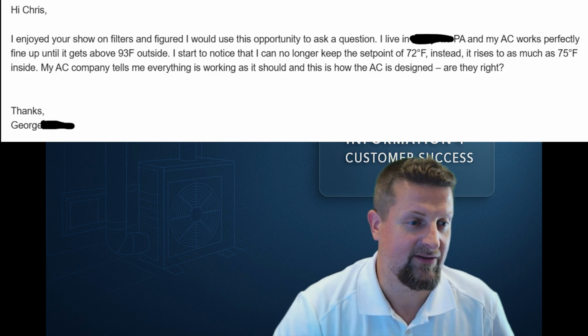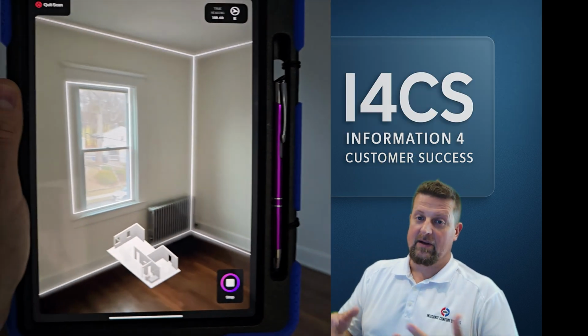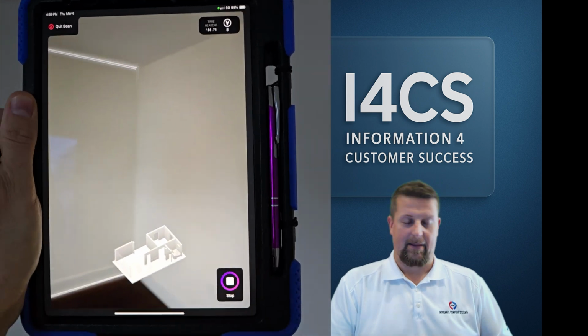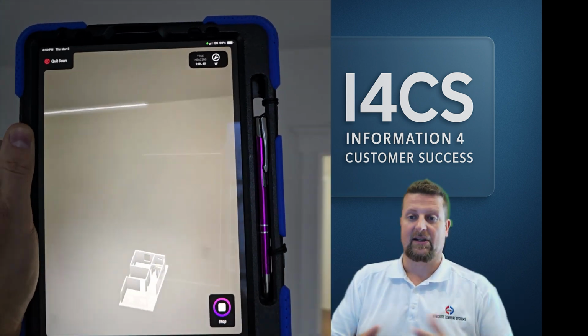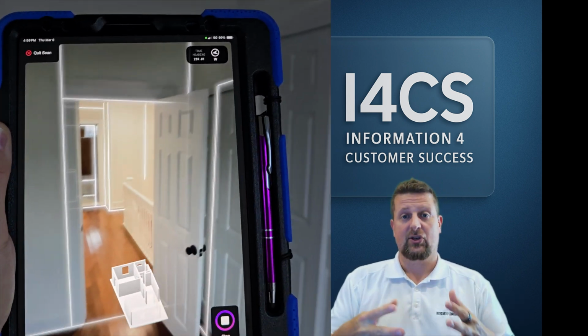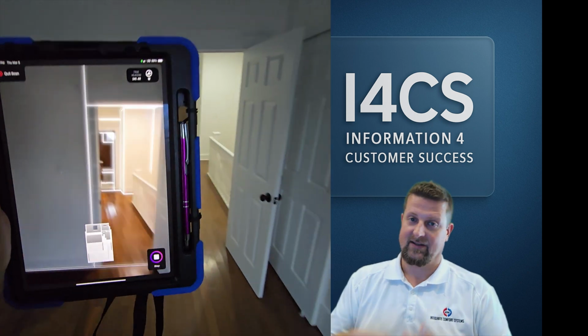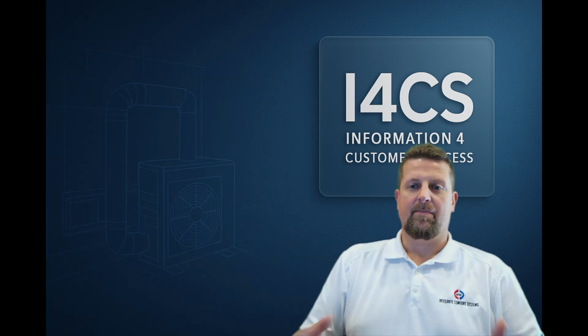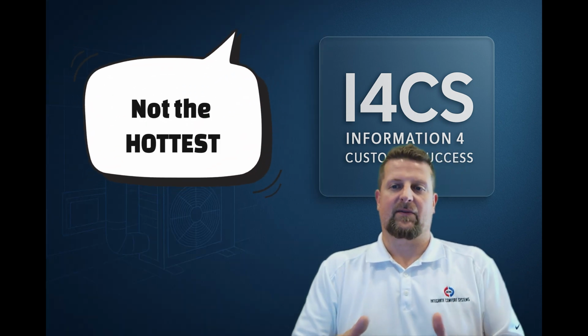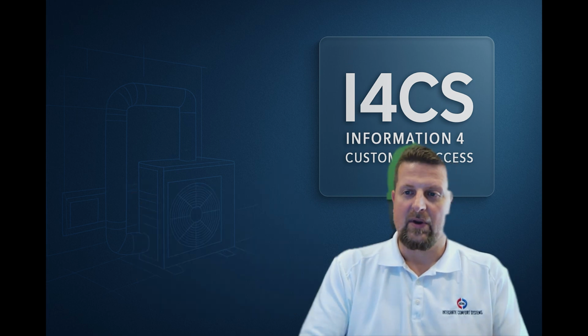Let me break it down. Let's start by explaining how every HVAC system should be designed. It should be designed using this thing called the Manual J. The Manual J is a heat load calculation. It is standard in our industry. The basic concept is that we don't size systems for the hottest or the coldest day of the year. We use what's called a design day, a temperature that represents a typical peak, not the extreme.